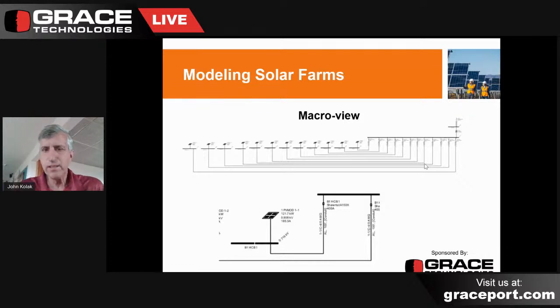Now, this is one place where I strongly encourage you to use the information you get from SCADA rather than just calculating the output of the farm. There are many cases, for example, where the voltage of the system is supposed to operate at 860 volts DC, and in fact, it operates at 916 volts all the time. So use whatever the actual data is on SCADA rather than just calculating the values, because it sometimes can be quite different. In this case, the engineer has aggregated all the feeders into the combiner boxes, and I think there are 12 combiner boxes that come into that particular inverter. So from a macro level, it gives you a view of how they chose to model the DC inputs into the inverter itself.